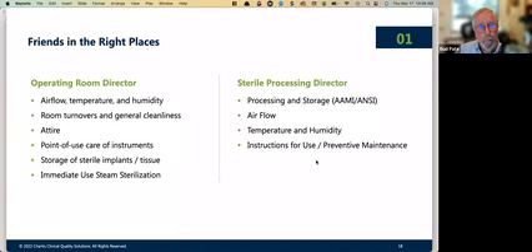One of the disconnects is that we're measuring humidity and temperature inside the room as opposed to at the supply duct. That's really where you want to measure it—at the supply end, not within the room. That's the first thing we do when dealing with this. Not every hospital has the capability of doing it that way, but that's what needs to be done.